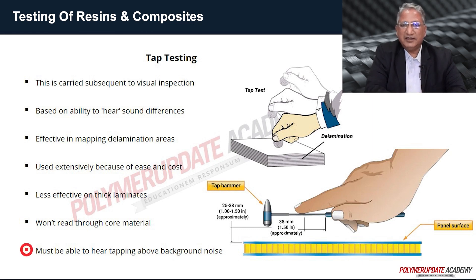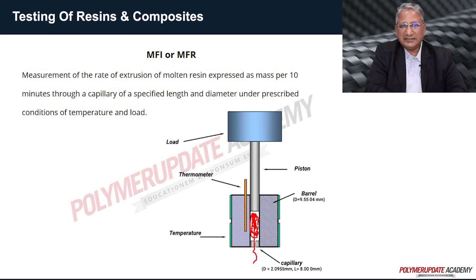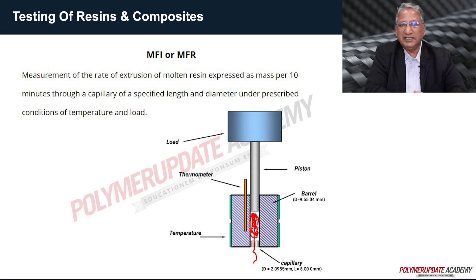For thermoplastic resin, melt flow index (MFI) or melt flow rate (MFR) is measured as the rate of extrusion of molten resin, expressed as mass per 10 minutes through a capillary of a specified length and diameter under prescribed conditions of temperature and load.